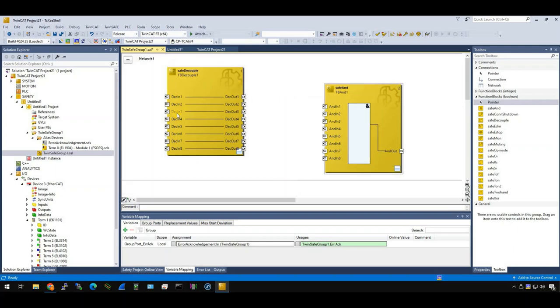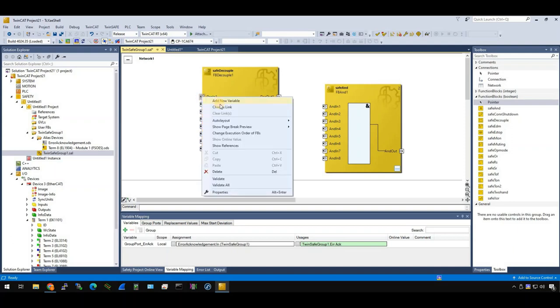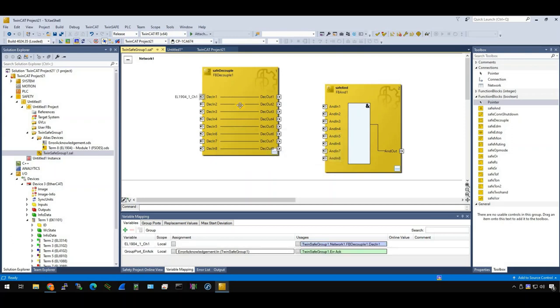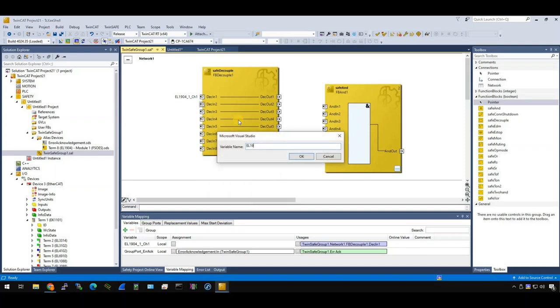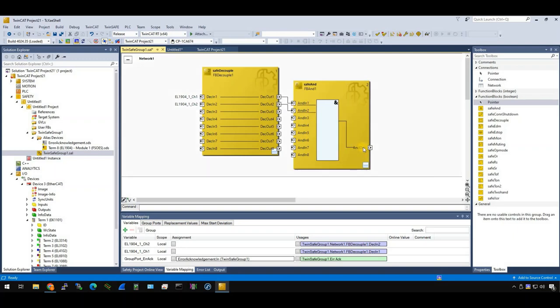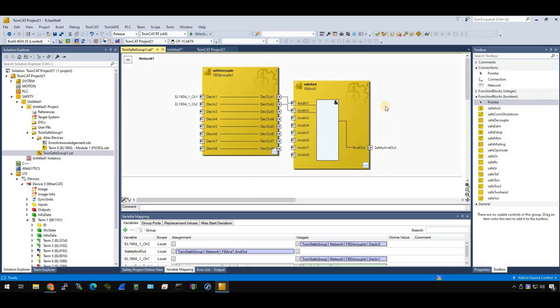Okay, now we can map these two signals into our safety project. What can we do? Just click the DecIn1, and right click, add new variables. Then you can enter any names you want. For example, EL1904_1_channel_1. That's up to you. Let's do the same thing. EL1904. This is the first one, channel 2. Yes. Okay, now insert two, create two variables here. Let's drop it in your AND function block. And finally, go to AND_OUT. Just click it, add new variables. For example, safety_AND_OUT. Done. Okay, now you create a function block.